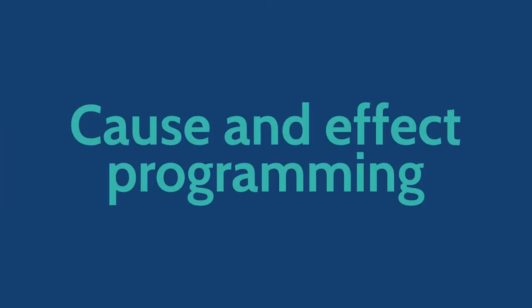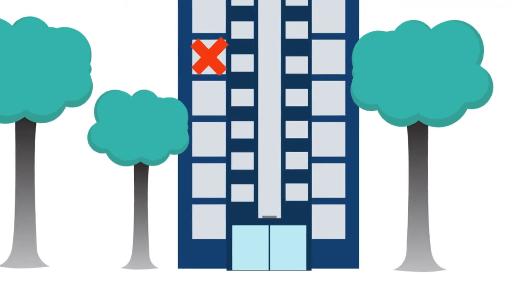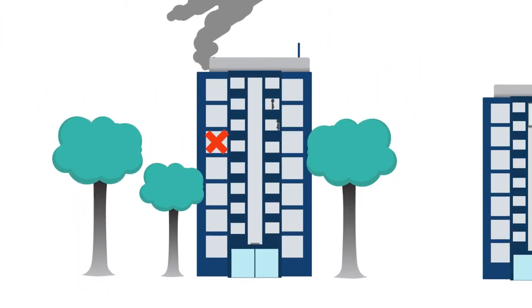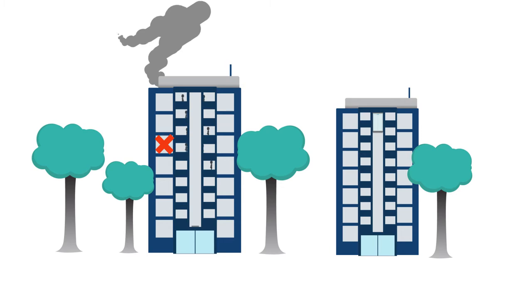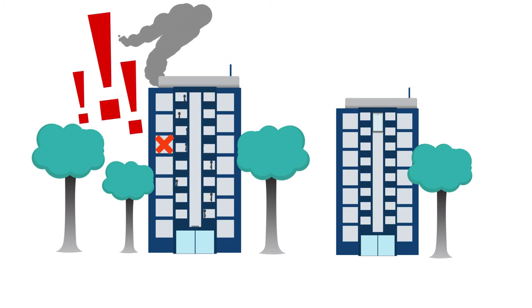Cause and effect programming enables the end user to decide what action they would like to take when an event occurs, such as when there are two office buildings side by side and if one building has a fire and is evacuated, the other building receives notification.